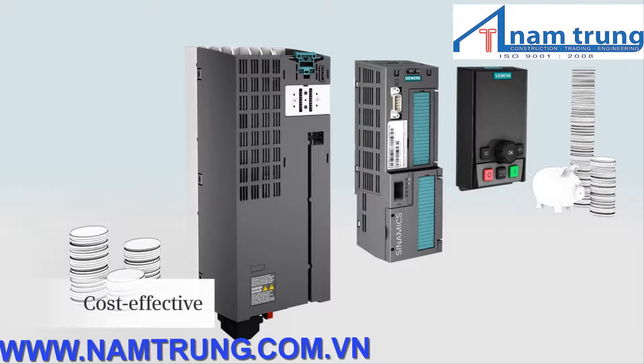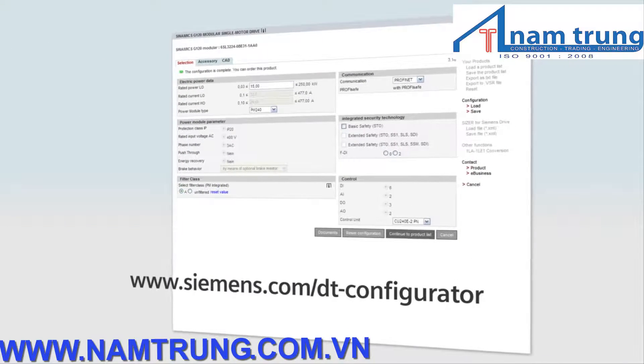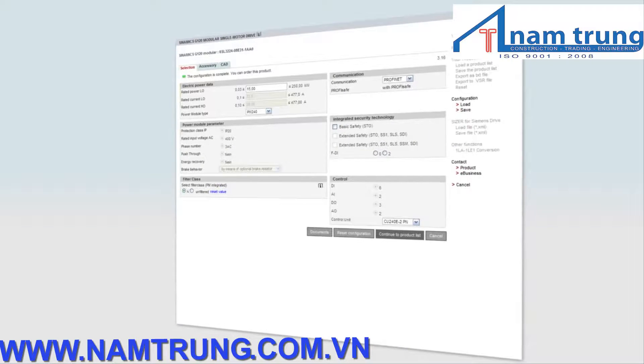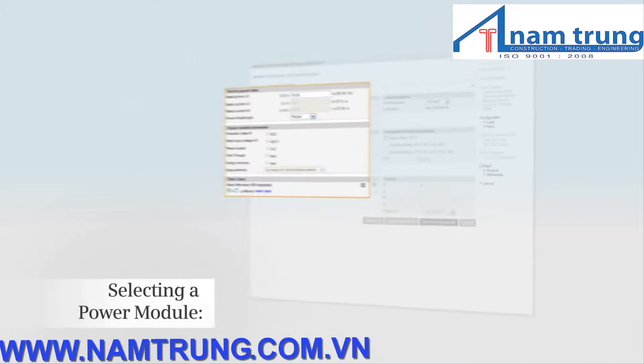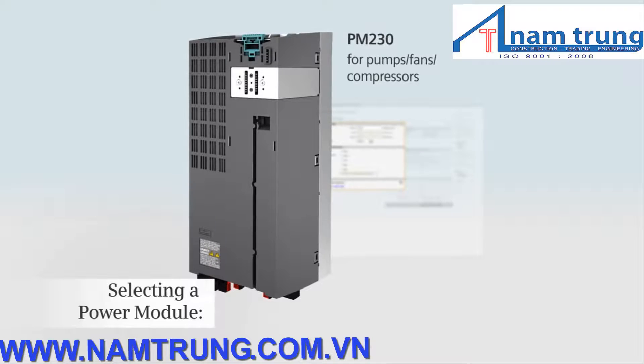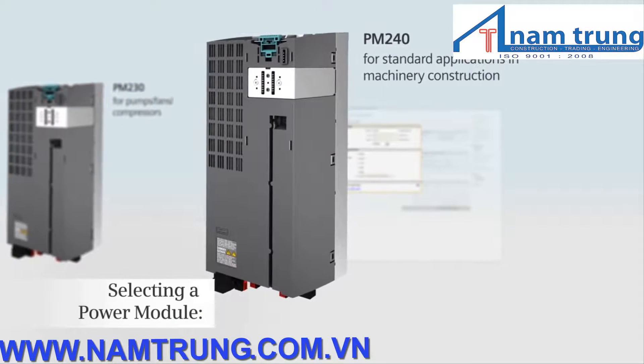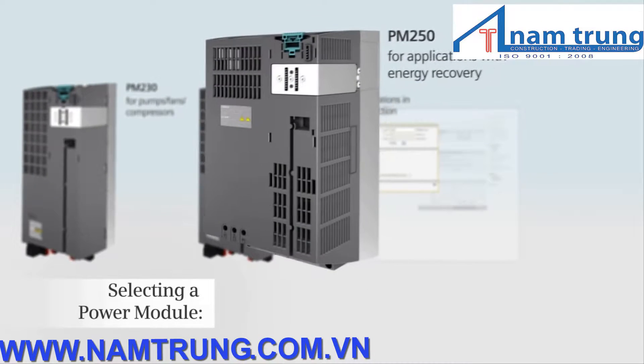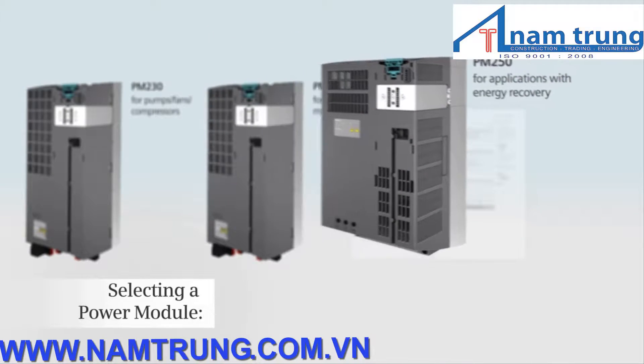How do you identify the components that you require for your particular application? You can configure your SINAMICS G120 with just a few mouse clicks using the DT Configurator, our online tool. First, select the optimum power module. Select a PM230 if you have a pump, fan or compressor application. Select a PM240 if you have a standard application in machinery construction, or a PM250 for applications with energy recovery — for example in conveyor technology.